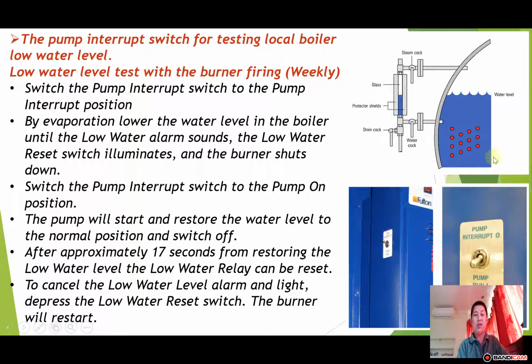So in the electrical control, the low water level relay will energize the circuit, and this will be reset into normal condition. To cancel the low water level alarm and light, depress the button, the low water reset switch, and the burner will start again.